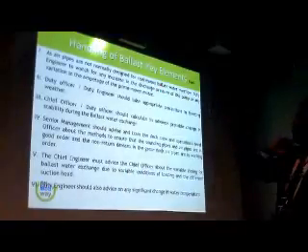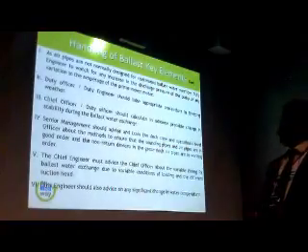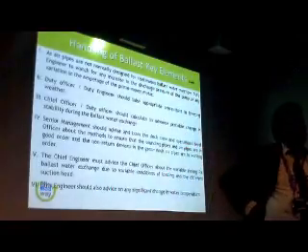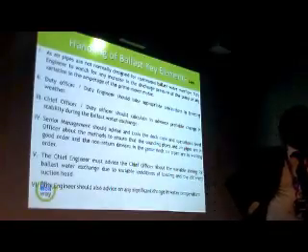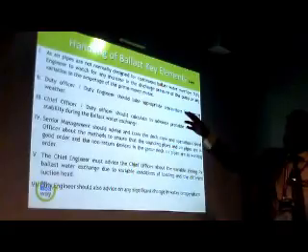So what we are trying to do is have the duty engineer or officer of the watch watch for any increase of discharge pressure of a pump, and variation of amperage on the prime mover motor. So if the amperes or loads are rising on it. Tomorrow in this simulation, I am going to create certain scenarios for you. I will be on the control panel where you will be dealing with those things.